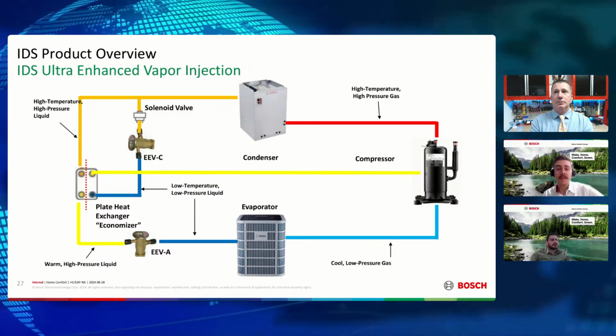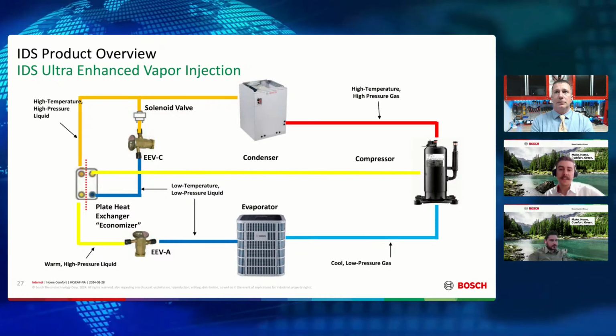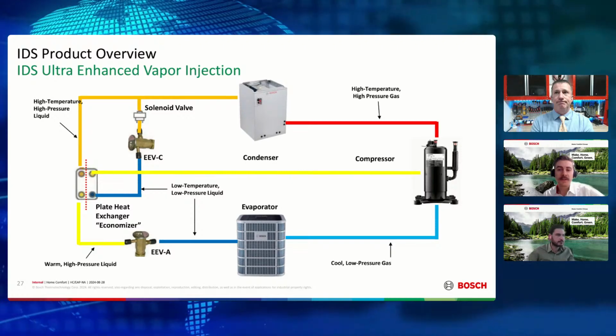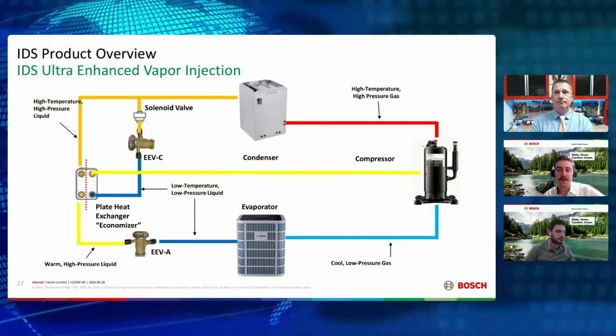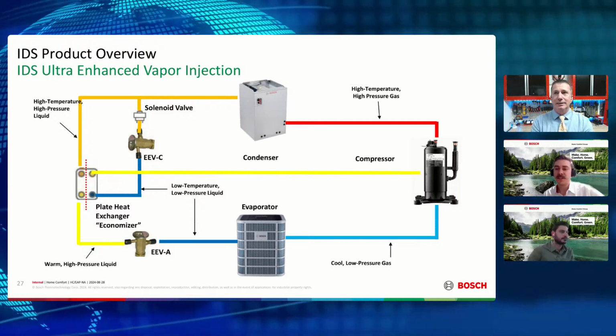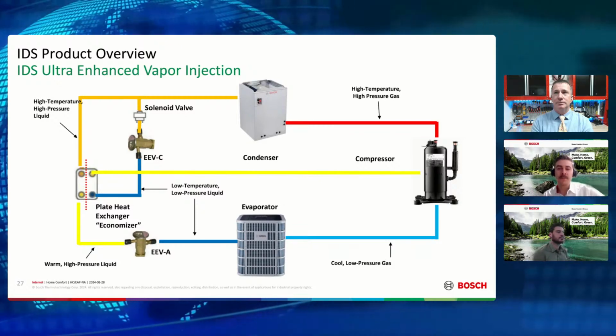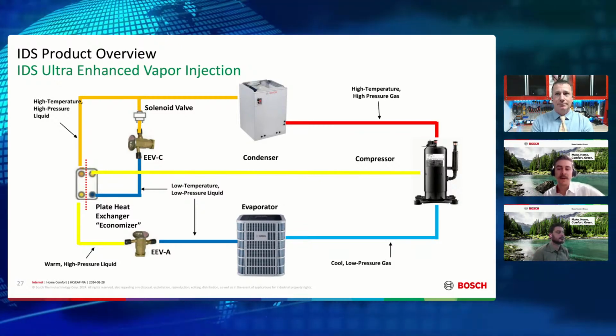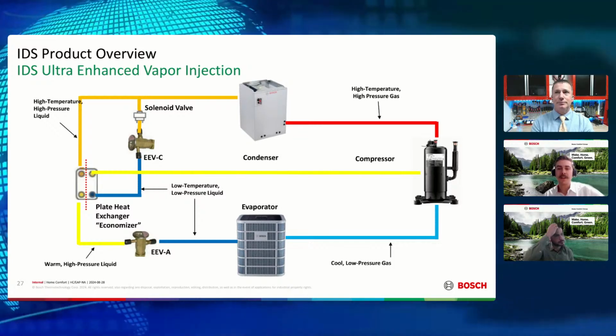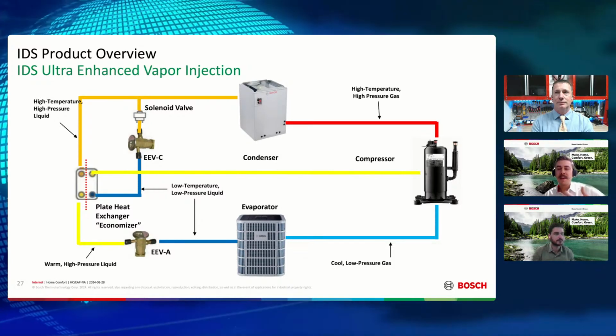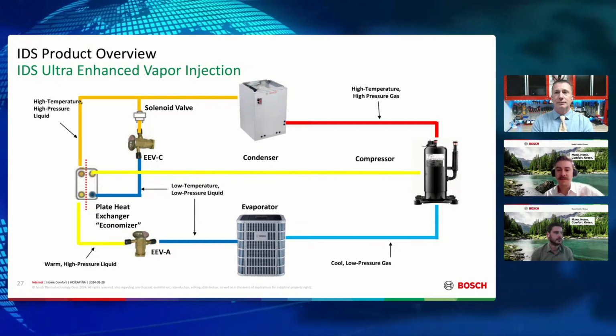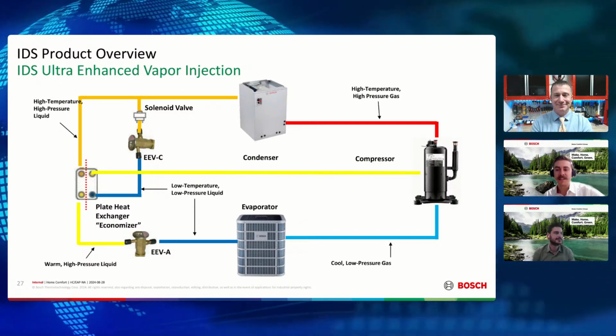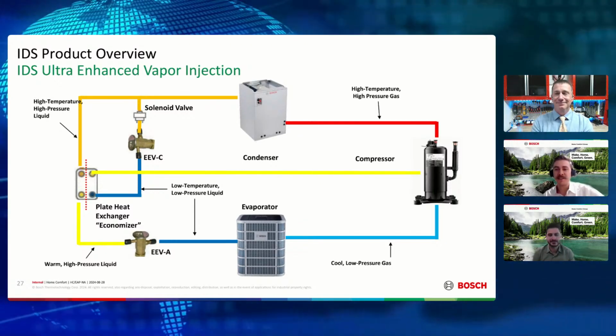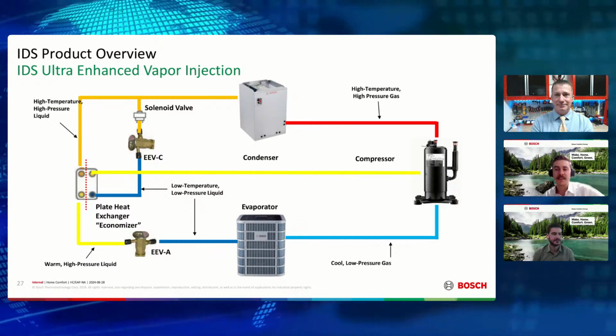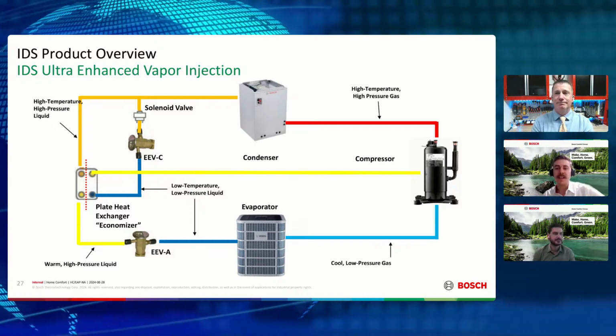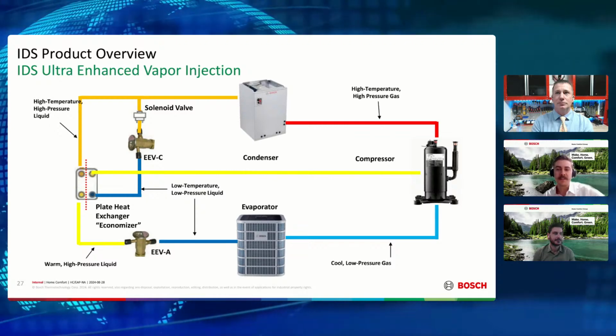One thing you mentioned before too, duct sizing and airflow. With inverters, if you restrict the airflow, you reduce capacity. Same thing again, because it's looking at that return refrigerant and modulating the compressor speed to match it so the vapor quality coming back is always the same. But if you reduce the airflow, less can boil off or condense, so it's going to modulate itself down. You need to make sure your ductwork is sized properly too. It's not going to want to overcome that on its own.